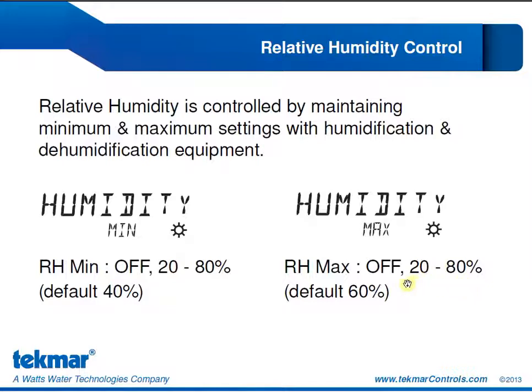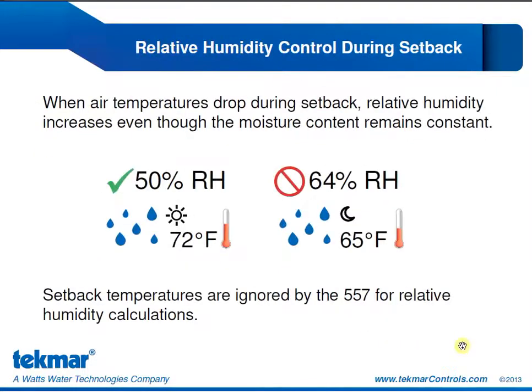Similarly with the maximum, we can configure it to 20 to 80%, or turn it off if we don't have a dehumidifier. The default in the 557 is 60%. If the humidity rises above that maximum setting, we may notice condensation on the windows. We might be worried about mold and bacteria. So we are going to enable a dehumidifier. The dehumidifier will turn on whenever the humidity rises above that maximum setting. And it won't turn off until we are 5% below the maximum setting. So the relative humidity is maintained with a 5% differential above the minimum and below the maximum.